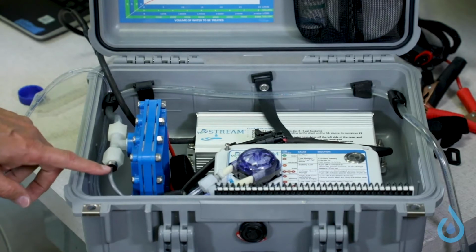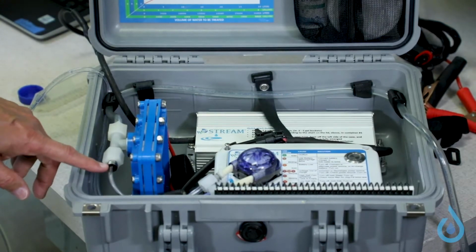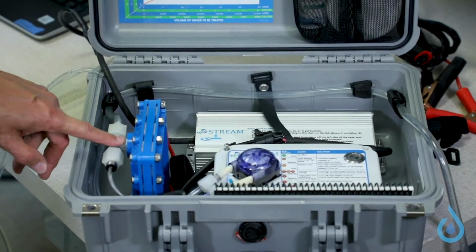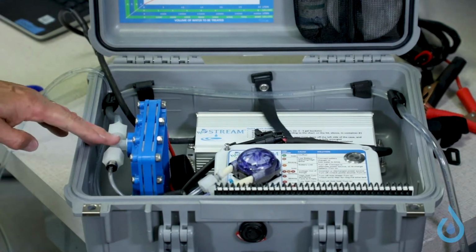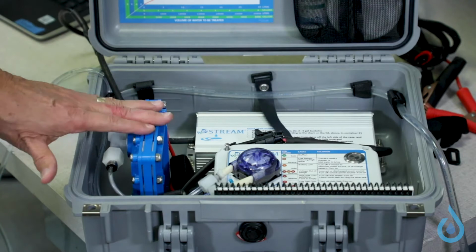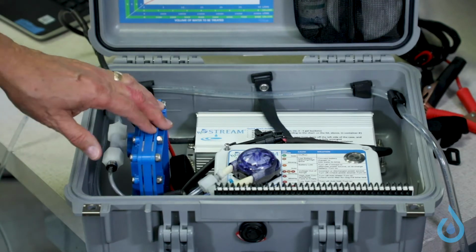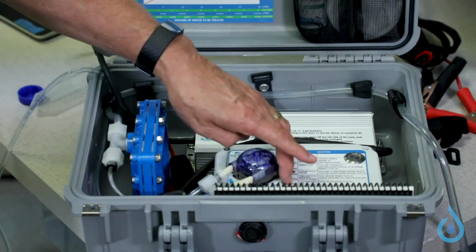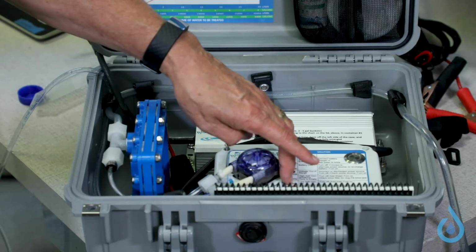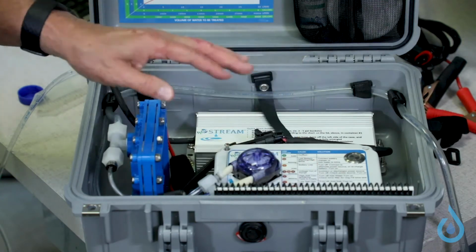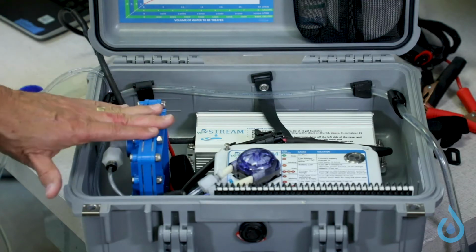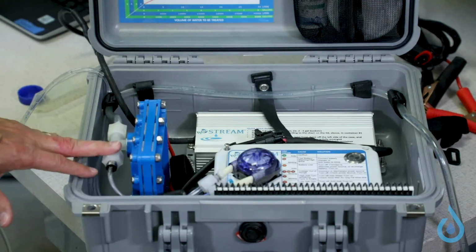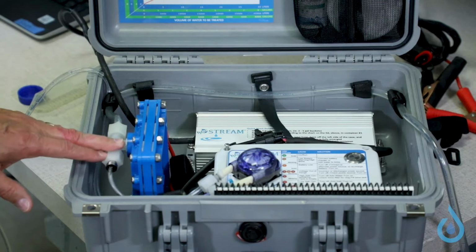So we have a thermowell. This is a device that measures the temperature of the solution coming out of the outlet of the cell. And if it gets too hot, to protect the system from damage, this light will alarm as a flashing red, green, red, and the system will shut down. So that is the primary condition. It is an over temperature condition in the cell.